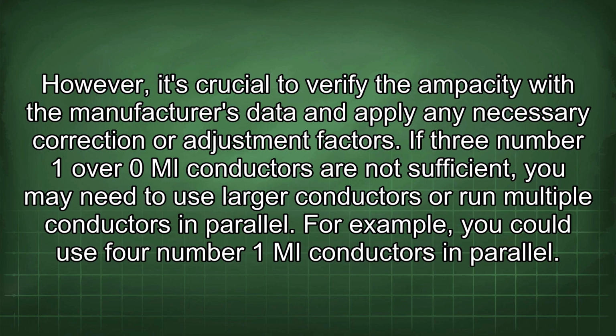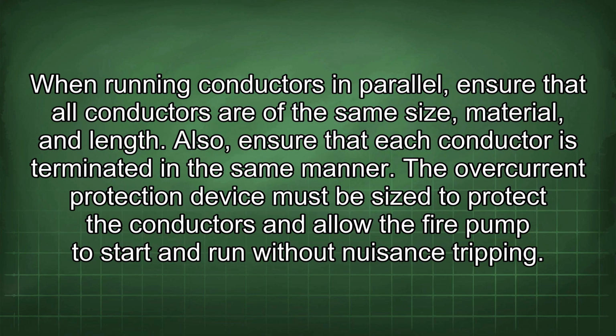For example, you could use 4 number 1 MI conductors in parallel. When running conductors in parallel, ensure that all conductors are of the same size, material, and length. Also, ensure that each conductor is terminated in the same manner.